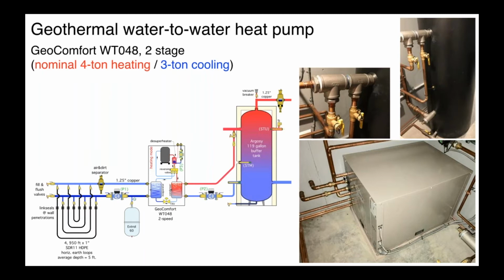water. So if you look at the pipes on this, there's actually 6 pipes connected to the left side of that heat pump. And these lower 2 pipes go over to a 38-gallon electric water heater. And that desuperheater will have the hot gas going through it. And there's a small bronze or stainless circulator built right into this heat pump that runs whenever the compressor is on, with the exception that if the domestic water temperature gets up to 130 degrees, that will actually shut off the circulator for the desuperheater. And that's just purely a safety device. So when this machine is running either in heating mode or especially in cooling mode, we're able to get a large percentage of the domestic hot water from the heat pump as opposed to the electric element in the water heater. So that little detail is shown here, the desuperheater and a small stainless circulator.